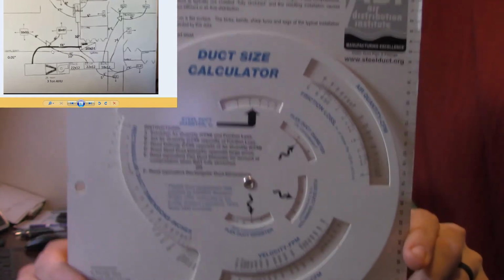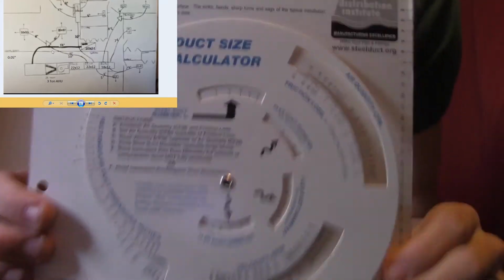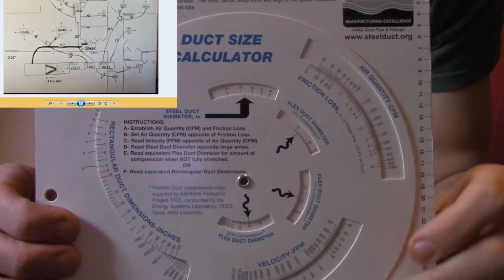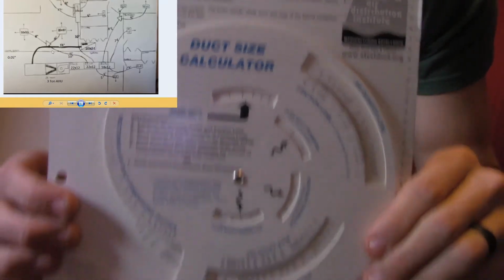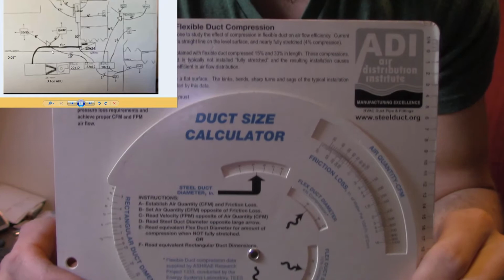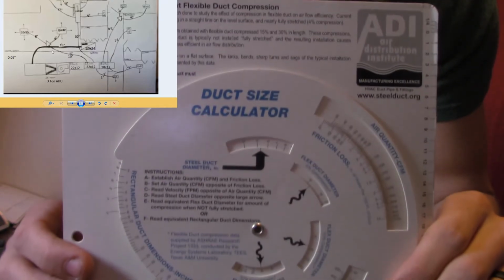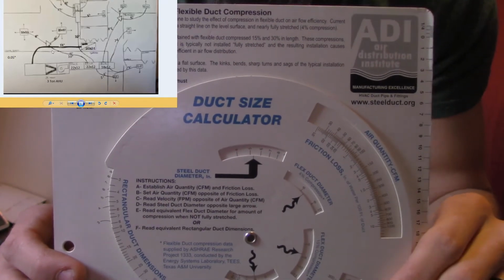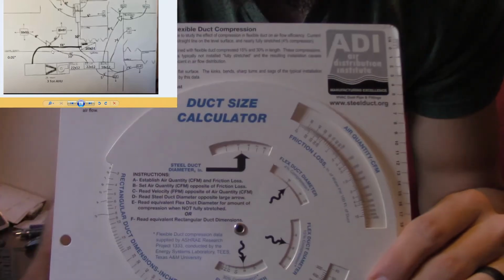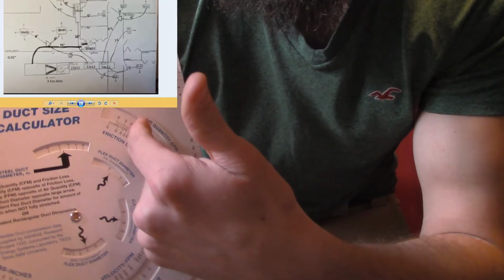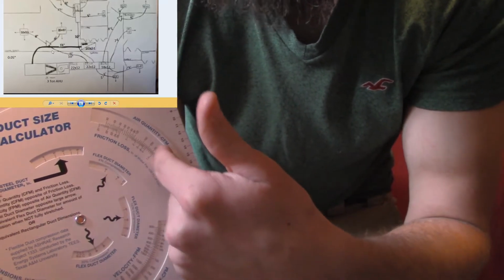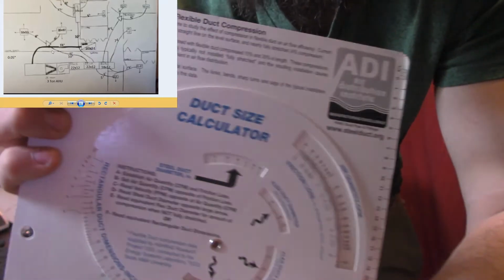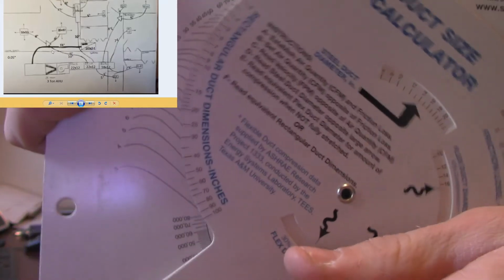And as a matter of fact, if you want one, I have a few in my trash can. But we're going to look at this one here. One thing I do like about this calculator is whoever designed it knows that flex duct is very, very seldom installed correctly. So what we're looking at here is we will look at our volume versus our friction loss. We will come up with some rectangular duct over here on the side of it.